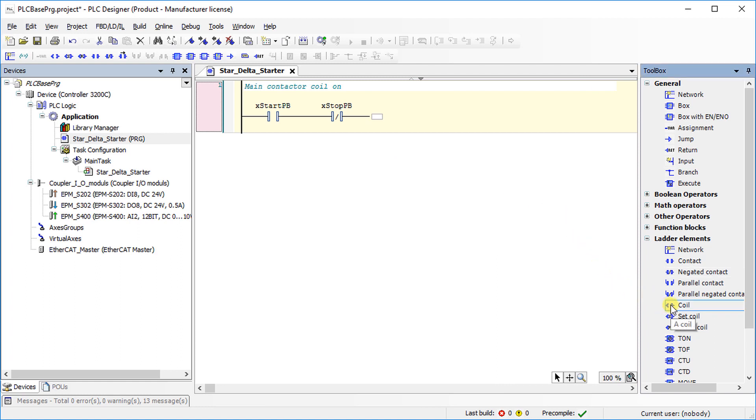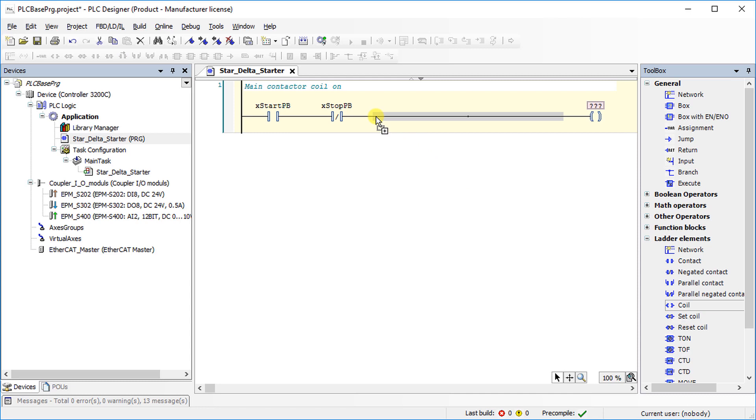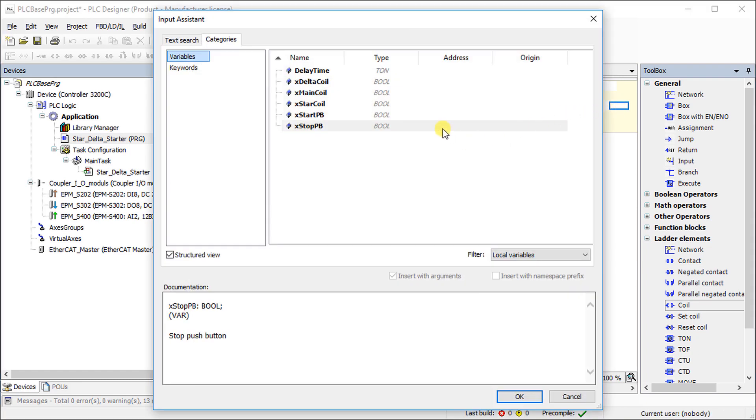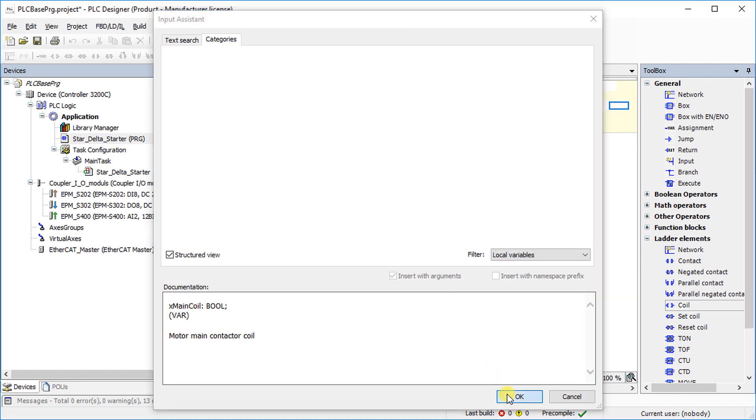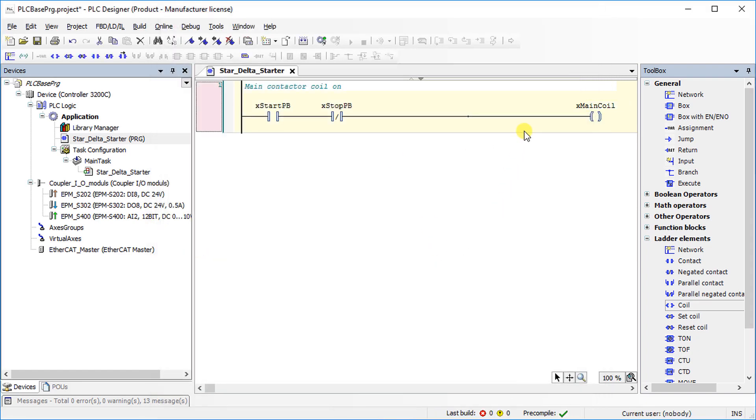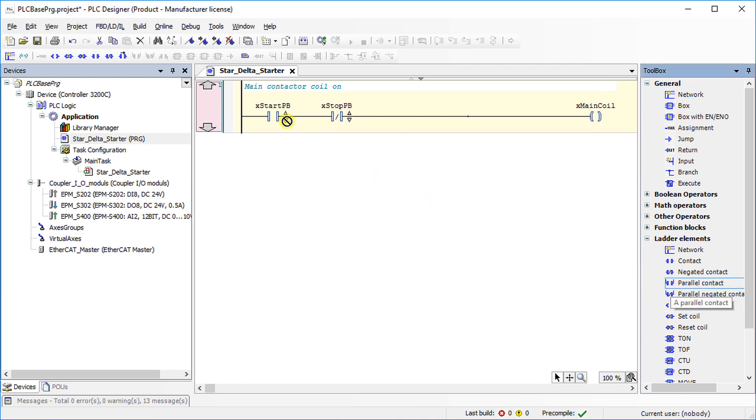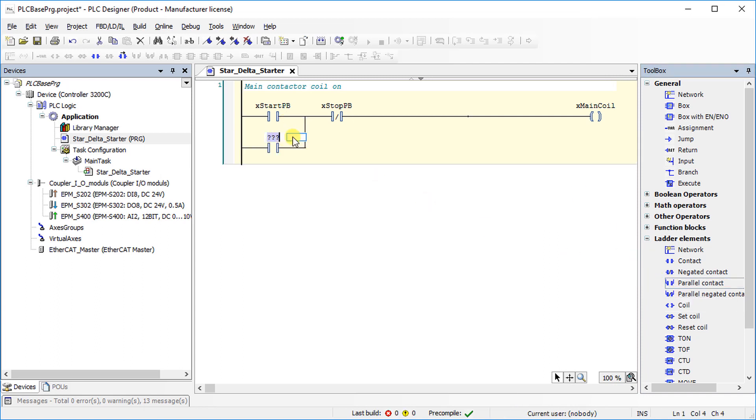For the output of the network, choose coil and add it in the series with the start and stop contact. Select main coil as output with the help of input assistant. Add parallel contact of main coil with the start push button contact to realize a holding logic.